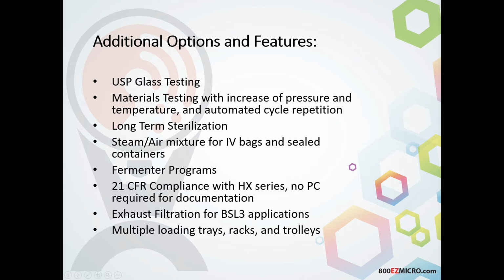We have the steam air mixture for IV bags and sealed containers such as blister packs. Specific fermenter programs with our HX system, so if you're using a full fermenter, we have a specific program for that. The 21 CFR compliance with the HX series. No PC is required for documentation. Everything is secure on a Linux-based system that is operated through the touchscreen of the autoclave. So you can have a network cable into the unit. It can send files directly to your network at the end of the cycle, but everything can be handled by an operator directly on the screen with signatures as well. So you can have counter signatures, so you can require as many signatures as you want on that document. Exhaust filtration for those BSL-3 applications, multiple loading trays, racks, and trolleys that can be accessories for the instrument as well.